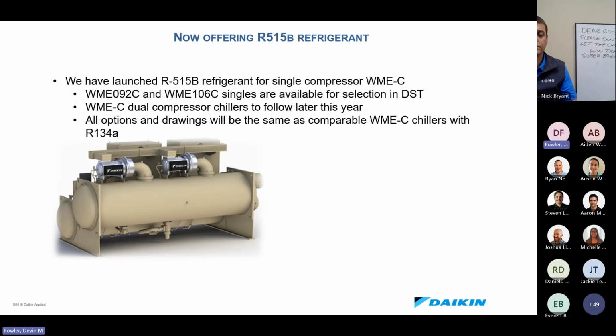Now we're going to expand on this product line with our 515B refrigerant operation. We have 515B refrigerant available in single compressor WME chillers. WME 092 and WME 106 singles are available for selection and purchase in DST. Our WME dual compressor chillers will be available later this year. We are rolling these out in phases as we complete our engineering and testing. All of our options and drawings for WME are going to be the same with 515B as they would be with R134A. However, you will have about a 25% capacity reduction when going from R134A to R515B.